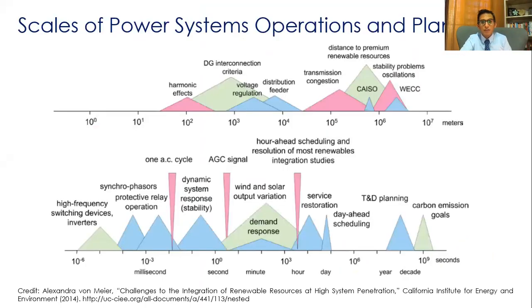I'll leave this graph for you to interpret at your own pace, in terms of meters. This shows what's happening next to the customer, who needs to take care of harmonics, maybe using filters. Next, in terms of distribution, we need voltage regulation, maybe FACTS devices, to take care of the distribution feeder and interconnection of distributed generation. Then there's the utility side.